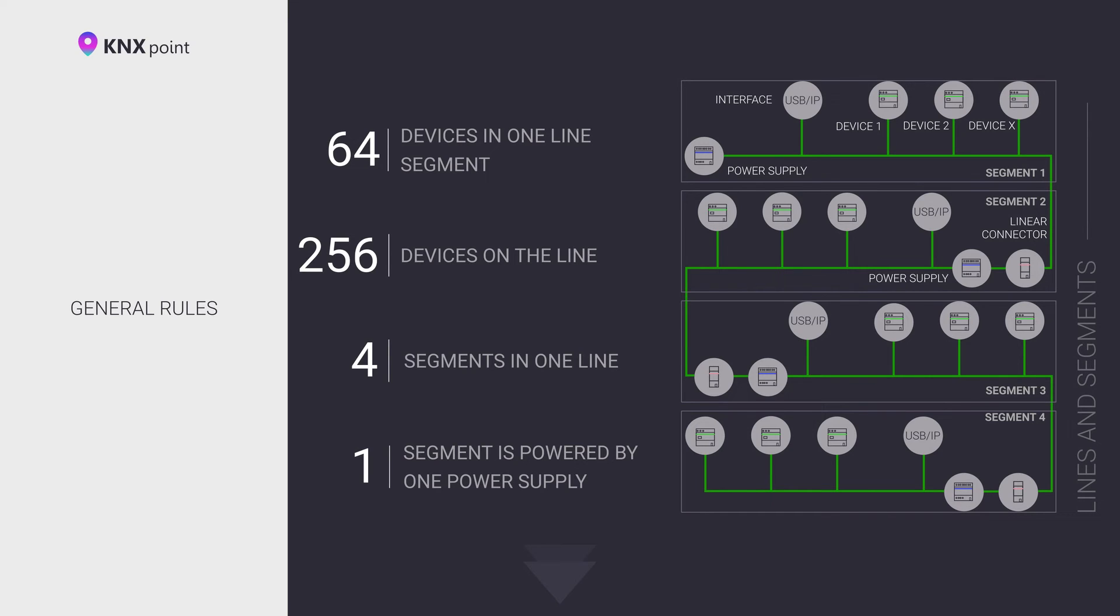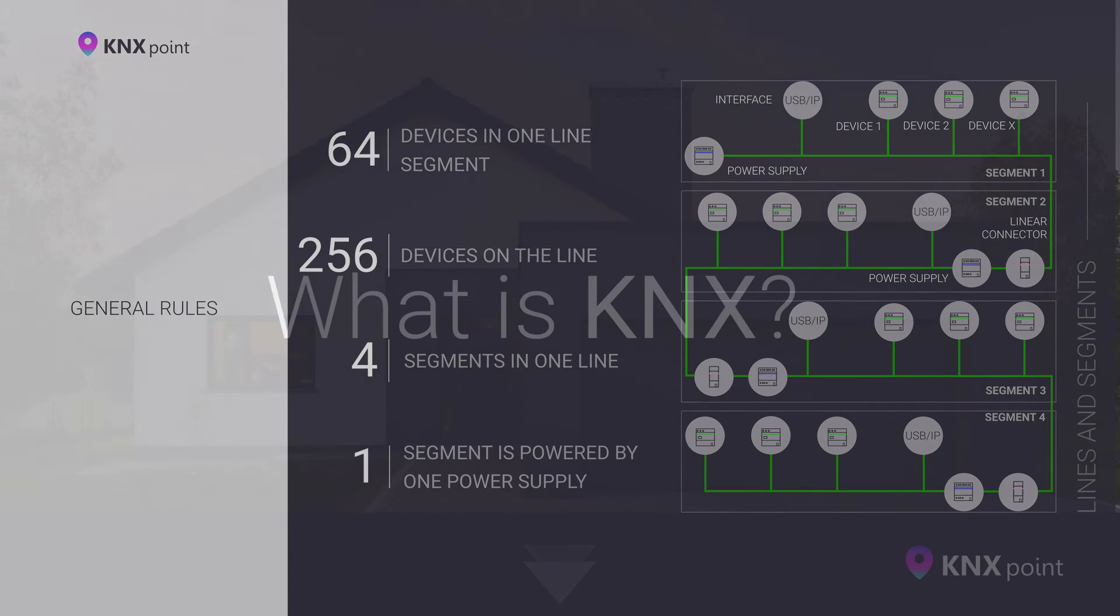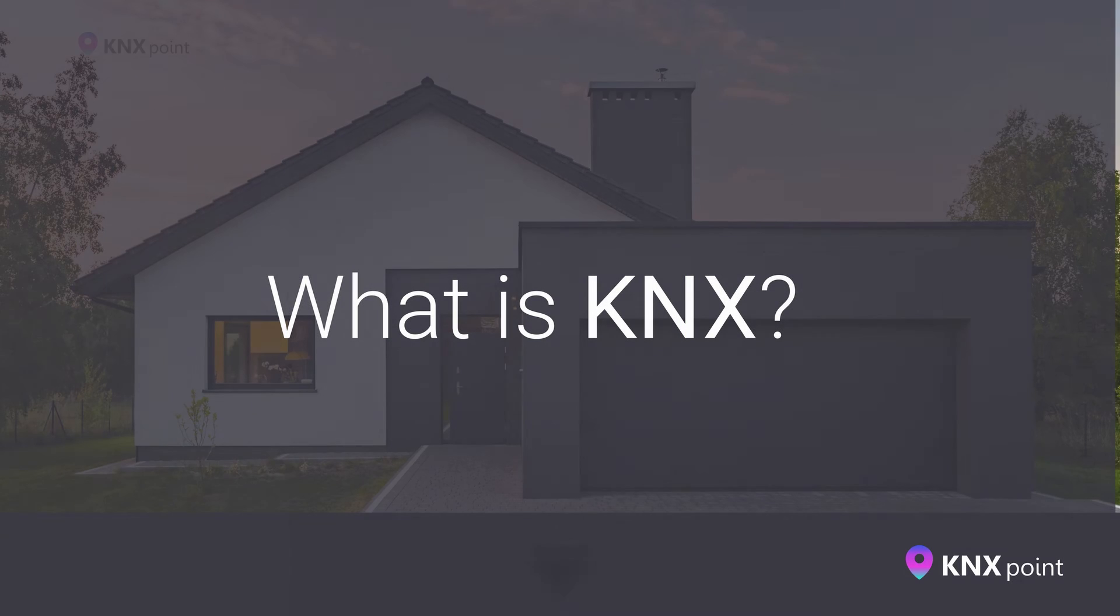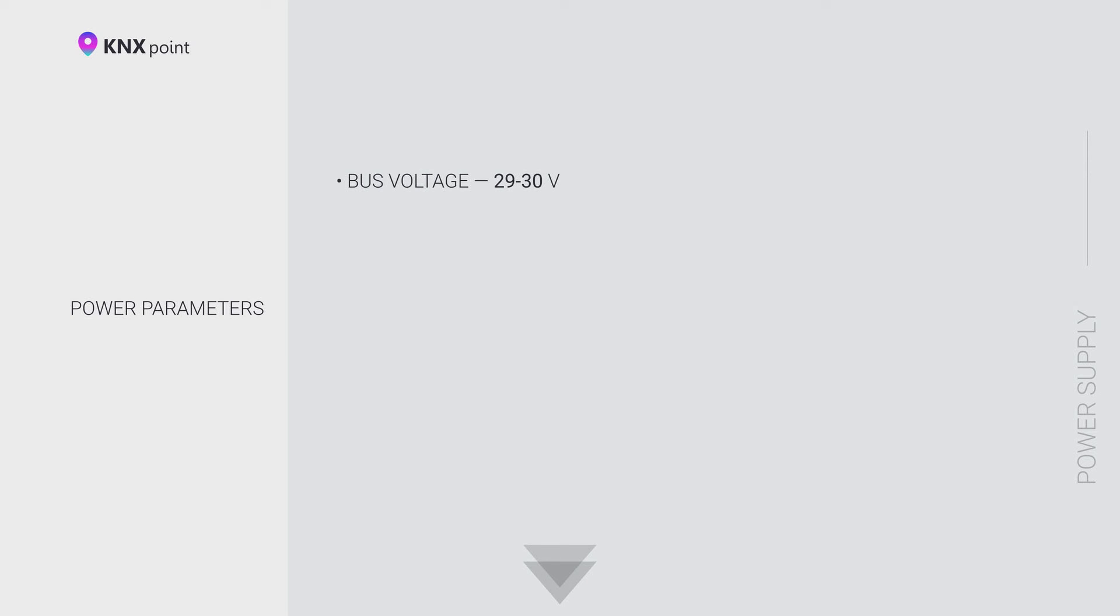Let's talk briefly about the supply voltage of the KNX bus. The voltage of the KNX bus is from 29 to 30 volts in normal mode, although the standard allows components to operate at a voltage of 21V. The voltage drop can be a maximum of 9V. On average, one KNX device consumes 10 mA.